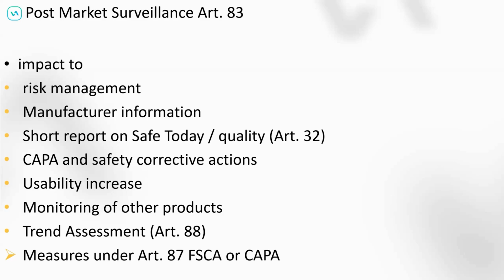If you look into risk analysis, there is a risk diagram which gives a lot of information about severity and probability of a certain risk. And as soon as you decide the risk is acceptable or not acceptable, as soon as you are with that particular risk, no matter how often it occurs, still above the line, or at least not changing your fields and going to a different probability group, that means our product is still sufficiently safe for the trend assessment. It does not mean that you don't need to add other things and ensure that your device can be better. It just means that you have a certain cover, a certain product safety, and that is sufficient for the current step. It does not mean that this is sufficient for you as a company and organization. Sometimes you need to do that on your own as well.